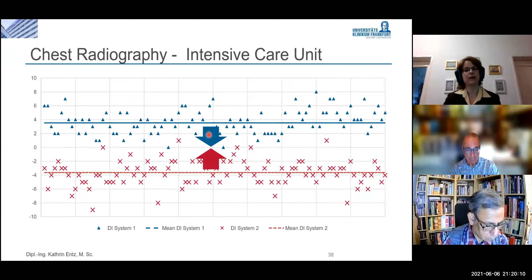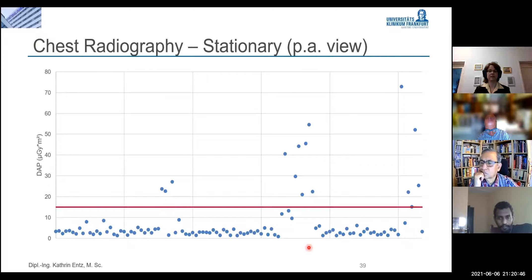And in the end, I'd like to show you another example, this time from our stationary equipment, again chest radiographies. And you can see here that the dose area product or the dose reference level of 15 is here, and that our normal values are also below this value. So again, we are good in most of the cases, but you can see that sometimes we are exceeding those values, and they're actually always going quite high.